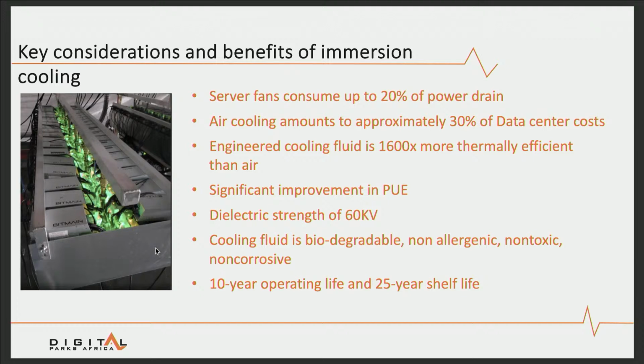Over and above that, in the data center we're finding about 30% of the costs, both on design and construction as well as operations, are spent on air cooling, so that is no longer required. Immersion-based systems, basically with a static tank and a low power pump, are able to bring a data center PUE right down to about 1.1, which is a really good PUE that traditionally we're not able to achieve in a data center environment.